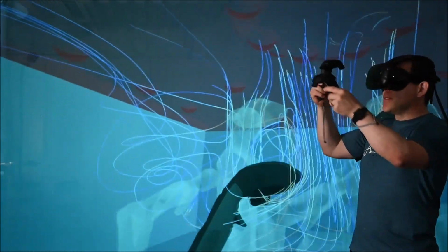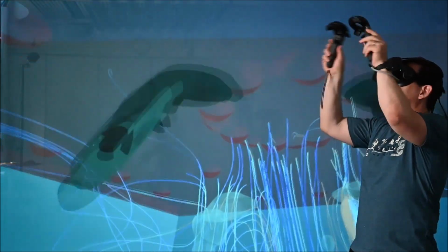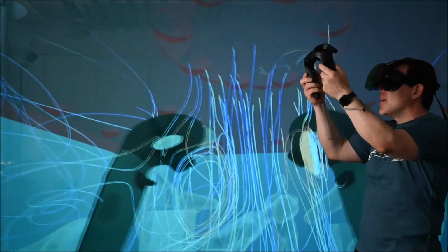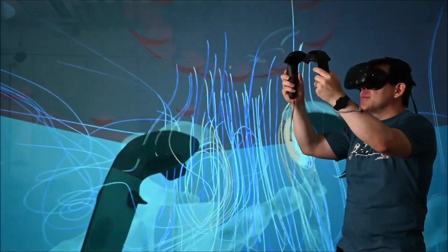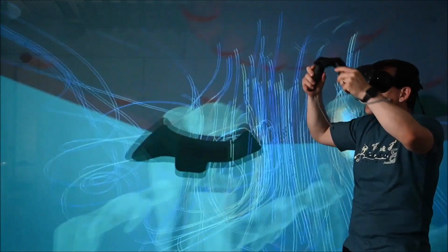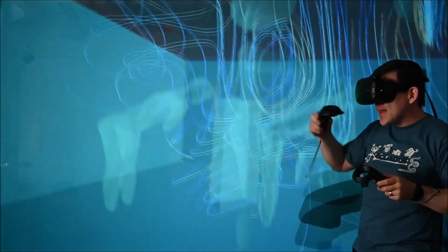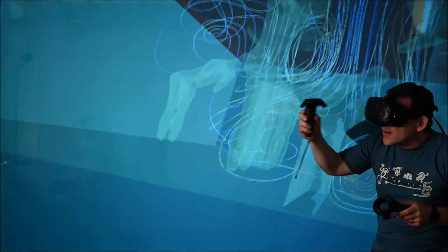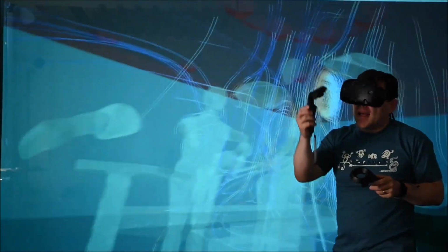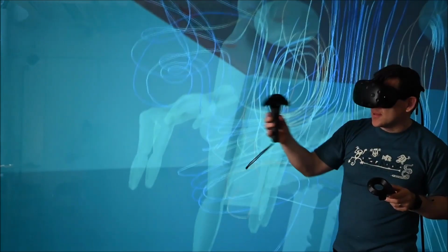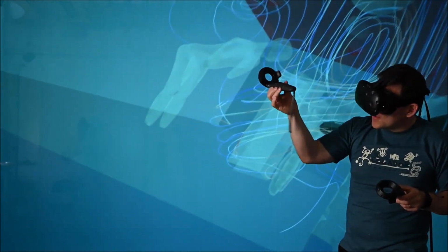Why are these vortices being generated here? One option may be that right underneath the airflow system, we have these 2 lamps, 1 and 2. And right underneath the lamps, we have these large vortices with high vorticity. Here we are visualizing with red that vorticity. Over here, right underneath the operating table, we also have this vorticity here. And this person leaning on top of the patient is generating vorticity underneath the torso.